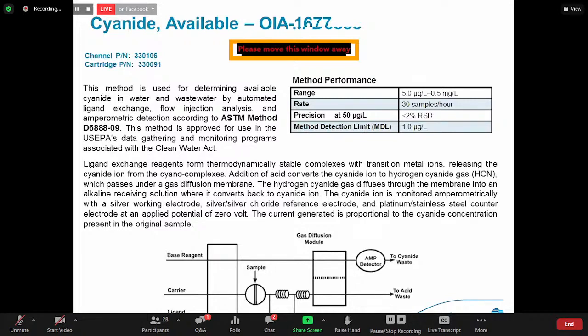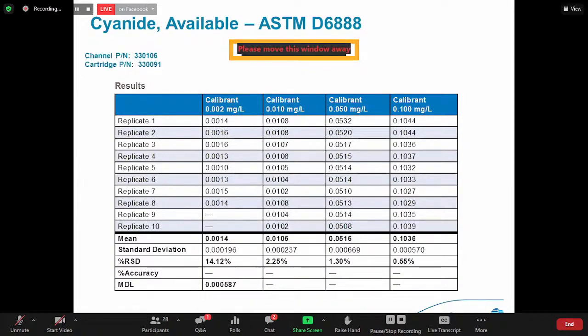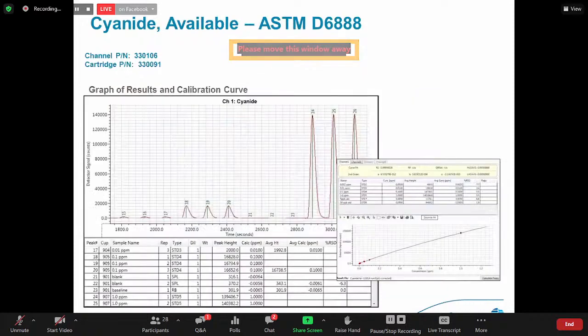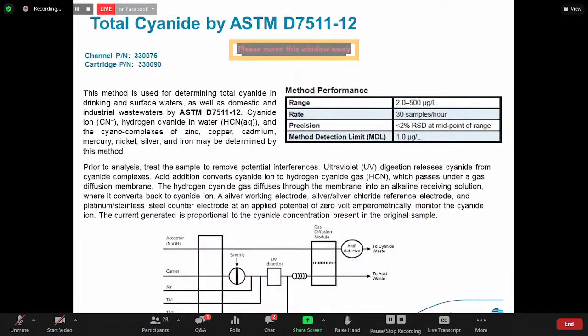Again, this is another one specific for 6888 and a different range. Here we have 5 micrograms per liter to 0.5 milligrams per liter. The same information is available of what the precision and MDL for this particular method should be. And this one, again, conforms to 6888 when the ligand exchange reagents are used. The same type of information is available in terms of the calibration in this particular method, and once again, the results from the calibration curve and what you can expect. And I think I have one more.